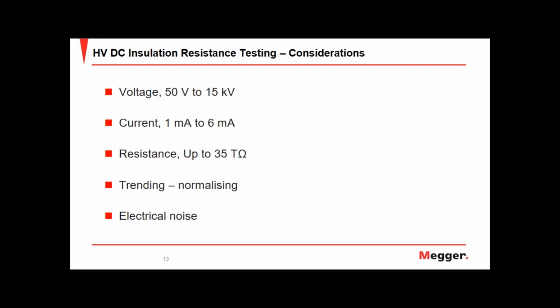It could be the wind changing direction and changing the evaporation of our layer of moisture on our asset. Okay, so things like that can be taken out using what we call averaging filters, and these can be switched on and off during the actual test itself and counteract and smooth the measurement.